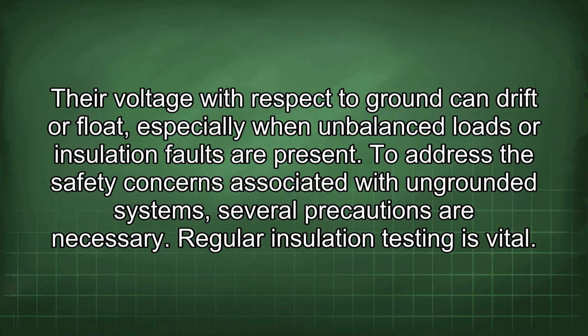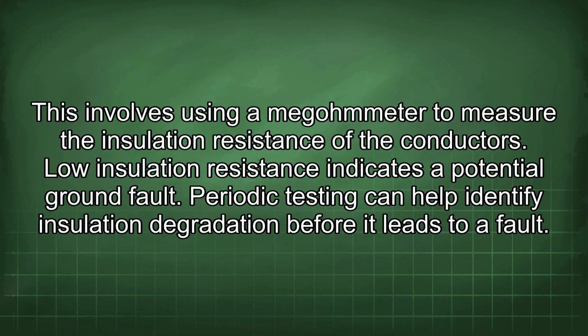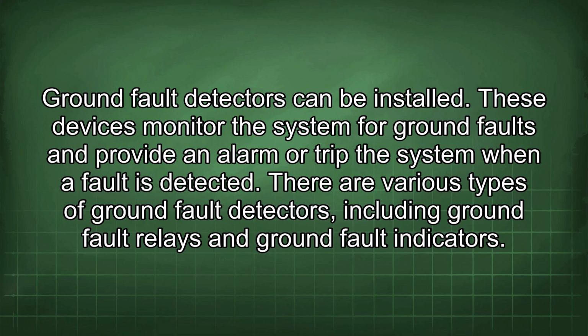Regular insulation testing is vital. This involves using a megohmmeter to measure the insulation resistance of the conductors. Low insulation resistance indicates a potential ground fault. Periodic testing can help identify insulation degradation before it leads to a fault. Ground fault detectors can be installed. These devices monitor the system for ground faults and provide an alarm or trip the system when a fault is detected. There are various types of ground fault detectors, including ground fault relays and ground fault indicators.